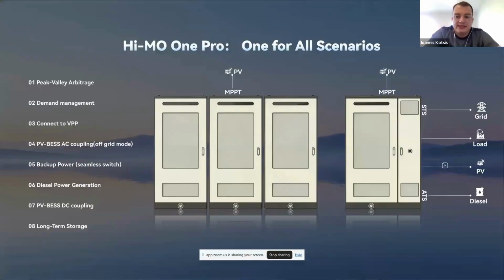Here you can have a better seeing. So, what can it offer? Of course, you know, the arbitrage, demand management, what I've talked about, off-grid mode with STS or ATS with diesel. And we can also have the DC coupling with the MPPT. So you can see that both, let's say, the master and the slave can get the MPPT if it's needed. So of course, this is optional if the customer wants.